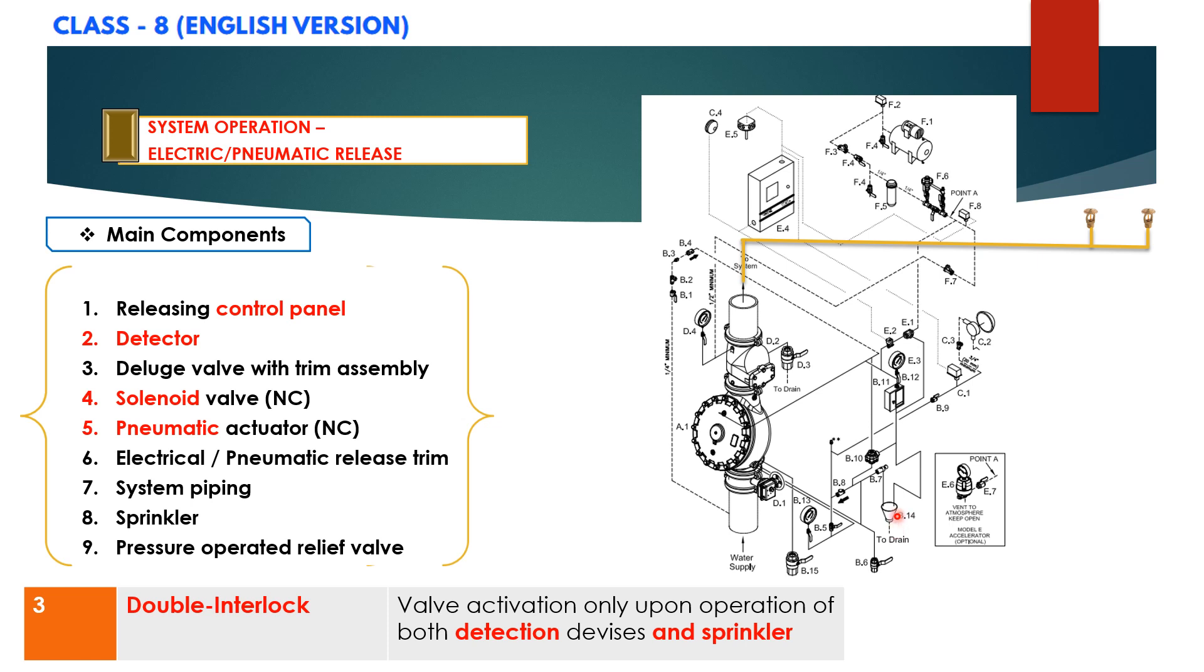When the PORV operates, it continually vents the priming chamber to prevent the deluge valve from resetting even if the open releasing devices close.